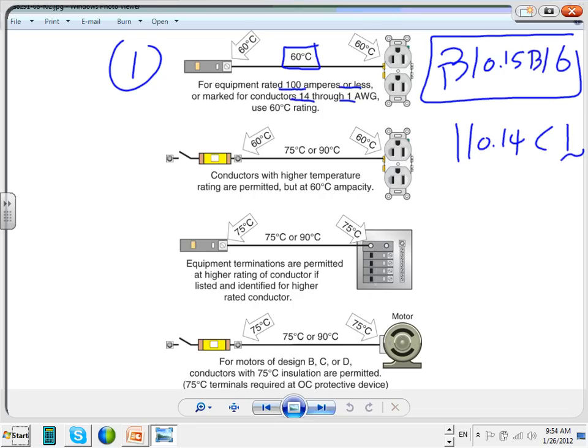The second one, guys: if the terminal is 60, and the conductors are 75 or 90, conductors with higher temperature rating are permitted, but we still have to size based on 60, because we size based on the weakest link. Look at the cable here, it is 75 and 90, but the terminals are 60. So which column am I going to go to under 310.15(B)(16)? Still 60 because of the weakest link. So this is number 2.